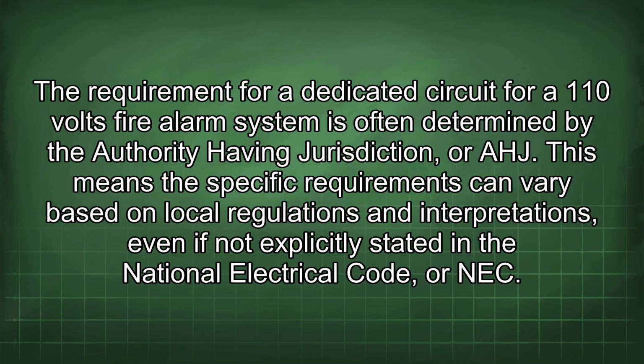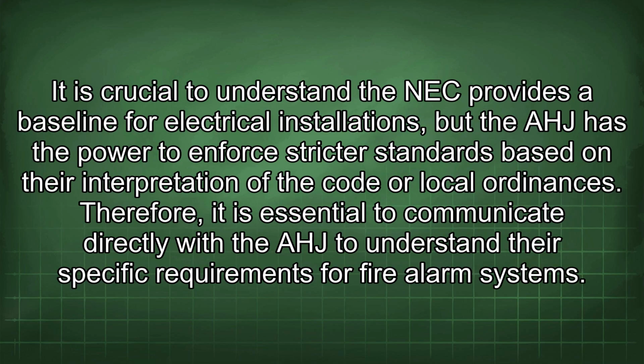The requirement for a dedicated circuit for a 110 volts fire alarm system is often determined by the authority having jurisdiction, or AHJ. This means the specific requirements can vary based on local regulations and interpretations, even if not explicitly stated in the National Electrical Code, or NEC. It is crucial to understand the NEC provides a baseline for electrical installations, but the AHJ has the power to enforce stricter standards based on their interpretation of the code or local ordinances. Therefore, it is essential to communicate directly with the AHJ to understand the specific requirements for fire alarm systems.